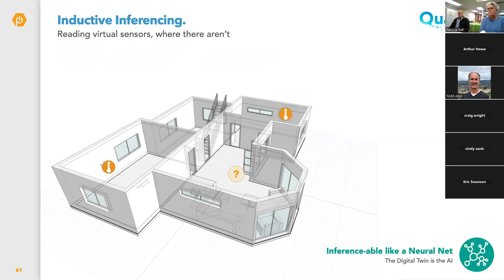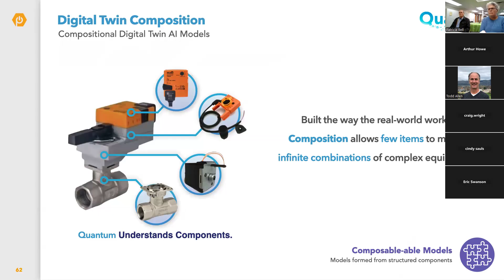Here's a simple control valve that we break down into four individual components. One is the valve that's actually stopping the water from flowing. One is the motor and actuator that's actually turning the valve. The next is the interface between the control and the motor, and finally the actual interface to the control system.